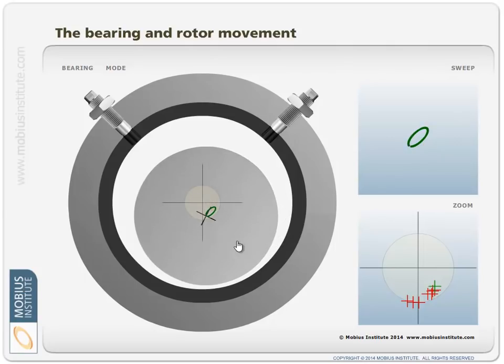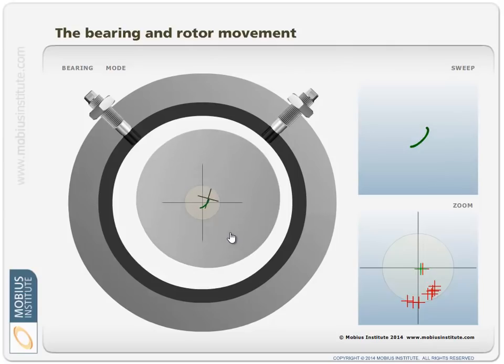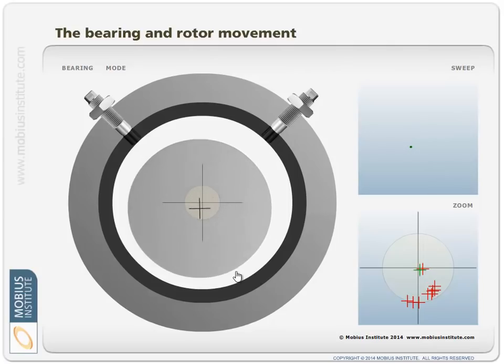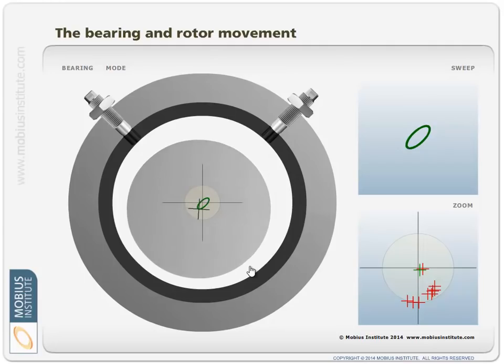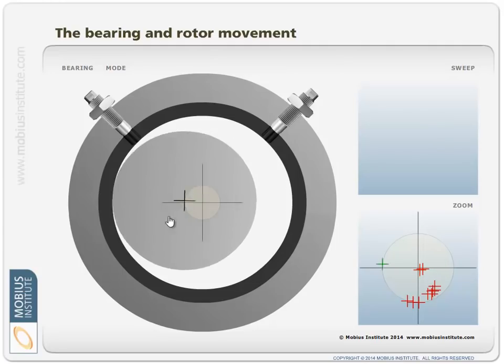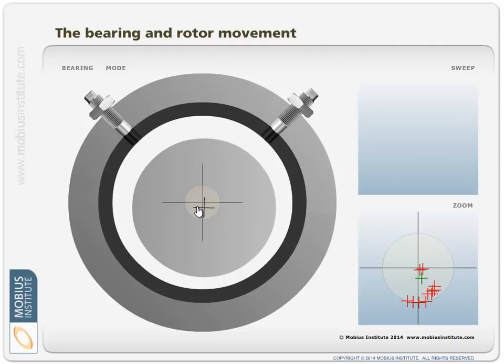If I see that it starts doing this, it's like, uh-oh, okay. What that means is there's not very much pressure on the oil wedge. This is no longer very stable. We can get oil whirl happening where the oil starts schlepping over the top of the shaft, and if that higher vibration that occurs as a result happens to coincide with the critical speed of the rotor, then we can have oil whip, and that's where the shaft potentially just starts chewing out the inside of your bearing. Anyway, lots of things we could talk about. That's why we run training courses.